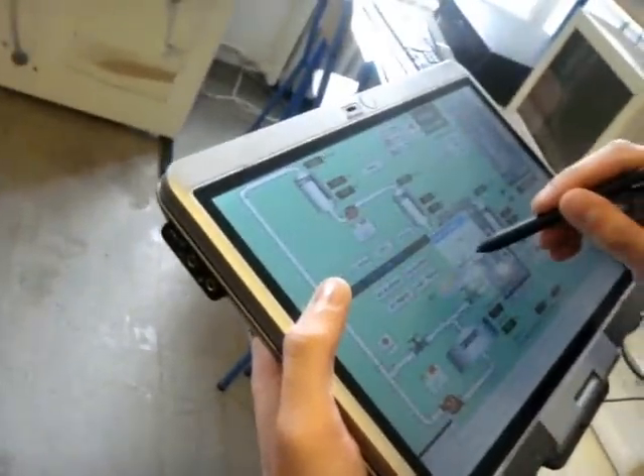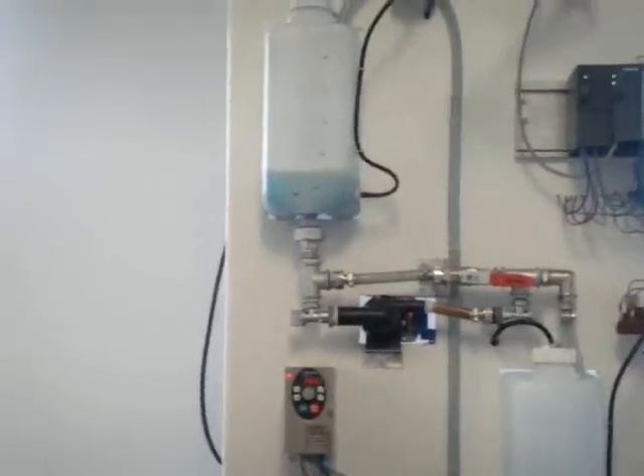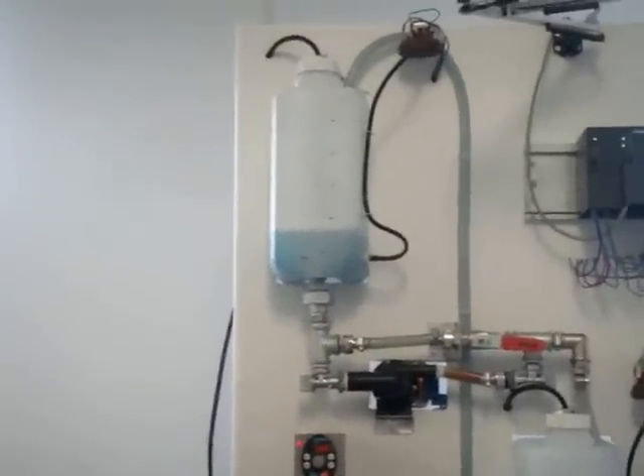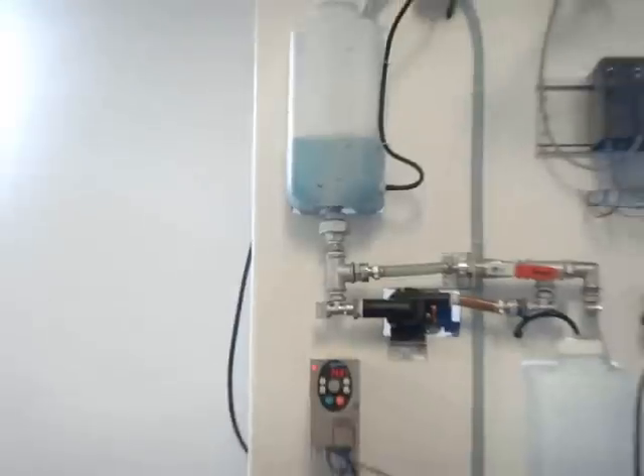Could you switch on the pump and give a set point of 30 centimeters? We put it at 30 centimeters and now we expect the plant to respond and the level in vessel one to increase to 30 centimeters. We see that the frequency controller is increasing the frequency — now at 27 Hz — to keep the pump running at the designated speed and the flow going into vessel one to the set point level.